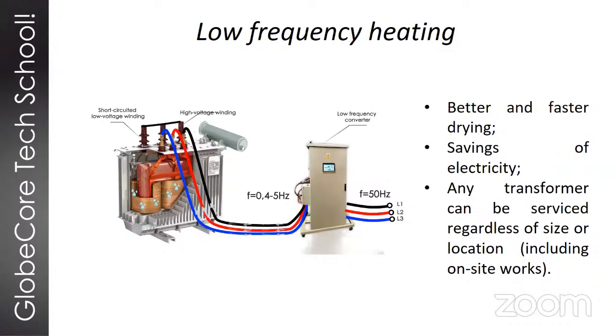It's important to have continuous monitoring of the temperatures of the high voltage and low voltage windings at the same time, to prevent breakdown of oil, because breakdown voltage is reduced in vacuum. It's also important to have a qualified operator running the system. For medium and large size transformers, the LFH method, the low frequency heating method, is used in combination with one or several other methods, such as evacuation, circulation of hot air, circulation of hot oil with spraying, etc. So it is the flexibility, efficiency, and versatility of the low frequency heating method that make it today probably the most promising method for drying of solid insulation in transformers.